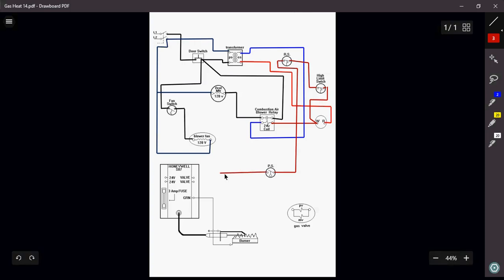Because now I am using my 24 volts. Again, remember, these are safeties. Okay, we need to make sure that this thing's going to operate safely. So in order to do that, my safety controls, my high limit switch, my rollout switch, and my pressure switch all need to be closed in order for my ignition module down here to receive 24 volts. In order for it to even receive the call for heat.